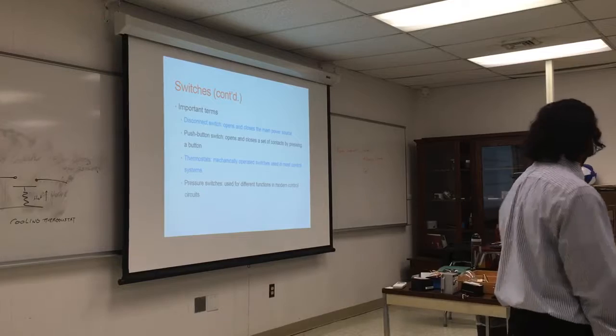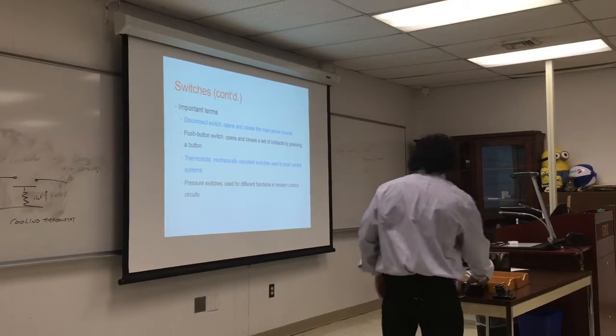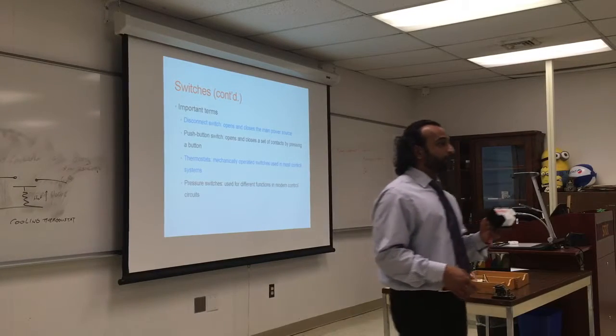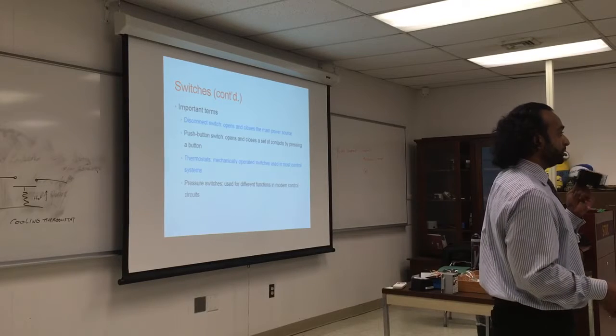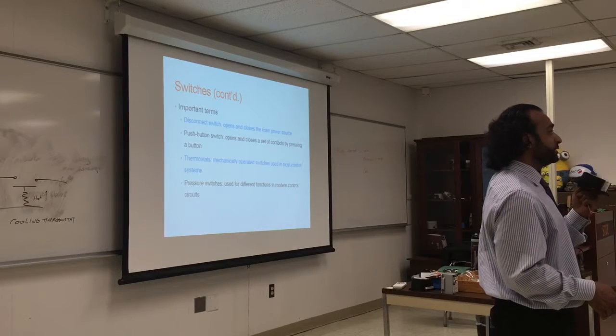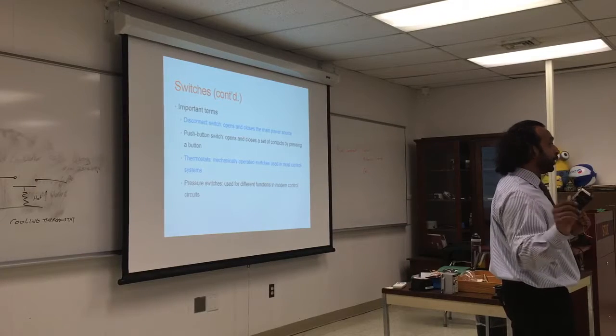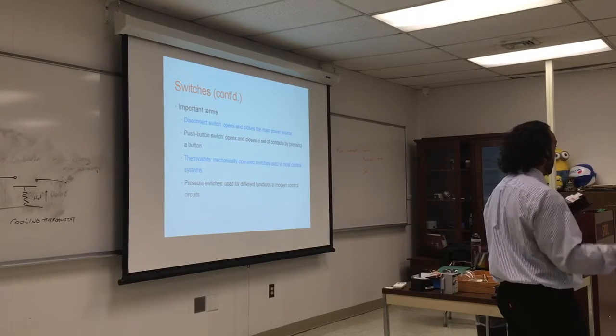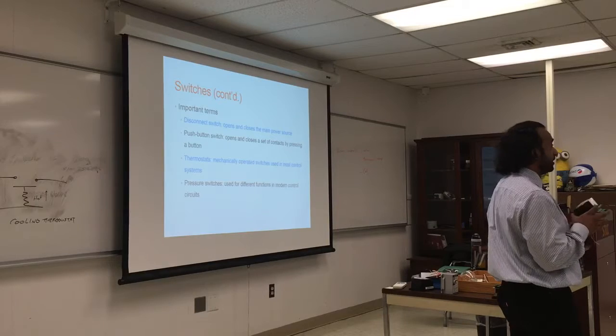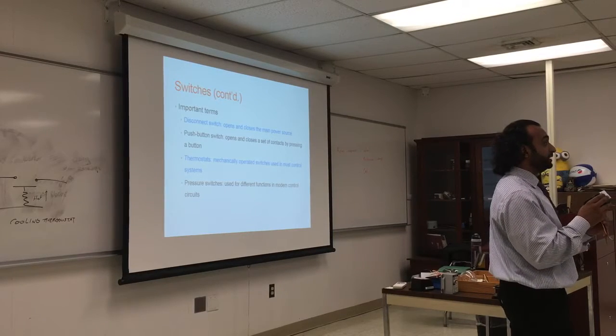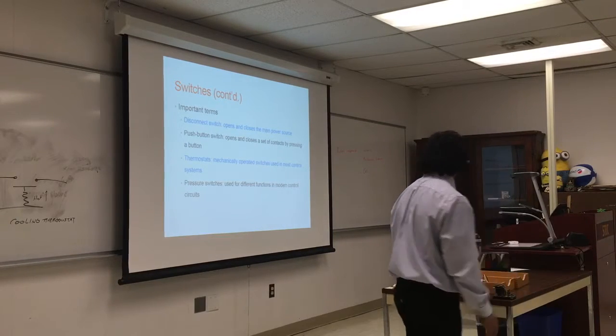You'll see that. This will become very, very visible when you work with the primary control, because it has a lot of decision making when it comes to burners. It will see the flame. Once it sees the flame, it will cut off the oil, cut off the ignition, and engage something else. So there are basically a few relays in here that are getting smaller and smaller.